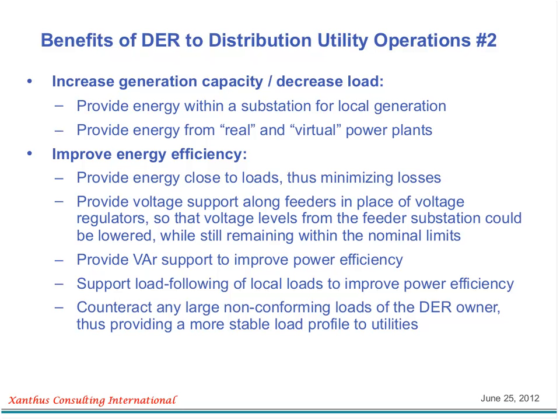This really will help handle the fact of millions of devices, and it will also help energy efficiency. You can now manage efficiency of the power system right where the problem is. If the voltage is a little too high, you can ask the DER systems to lower it. If the voltage at the end of a line has dropped too much, you can use DER systems to boost it up, on a much finer grain than using cap banks, capacitor banks, and other voltage regulator devices.